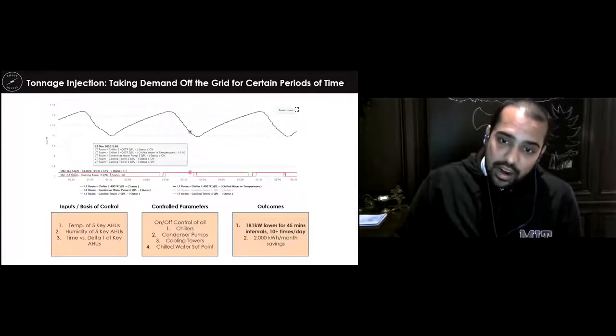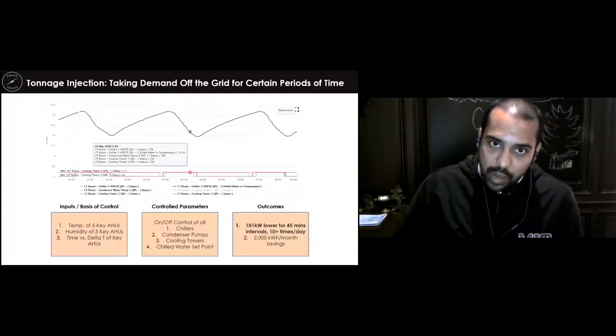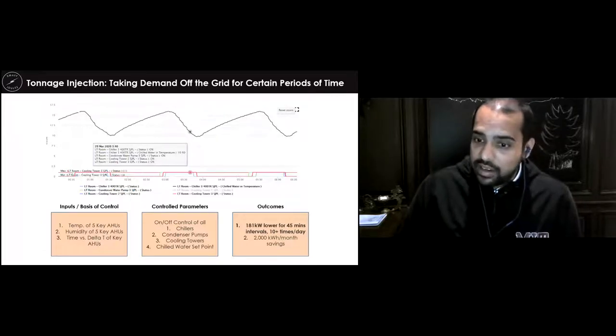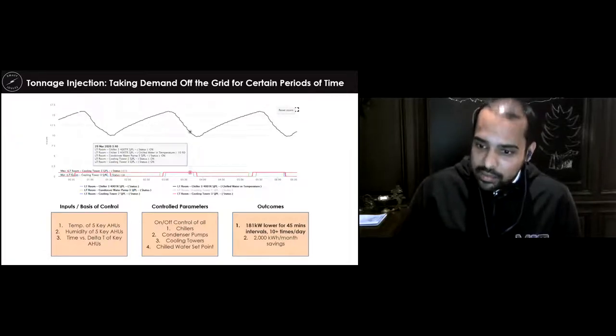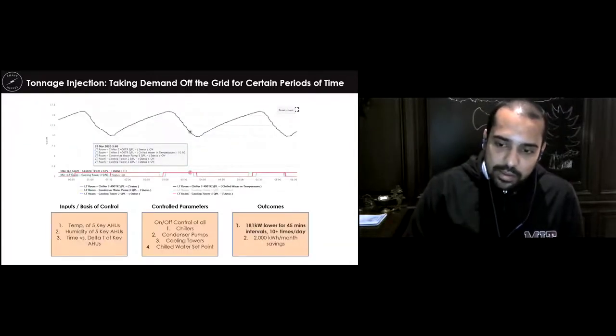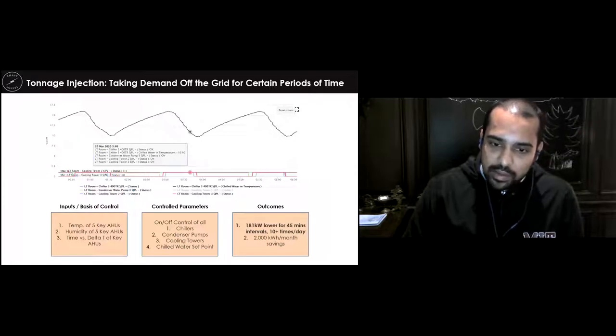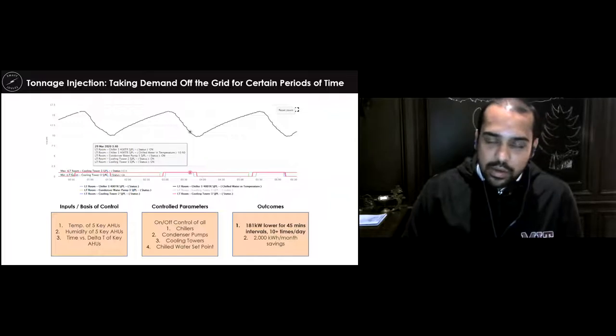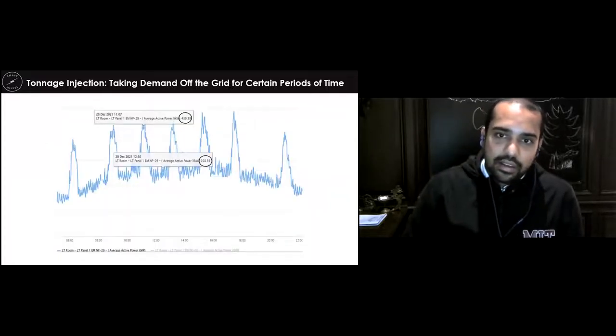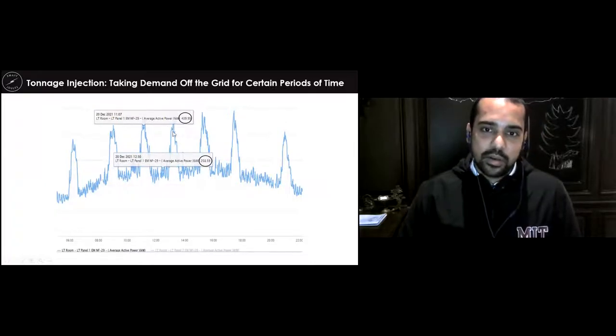In this particular example, 181 kilowatts of power were taken off the grid for 45 minute intervals each, more than 10 times a day. Typically you think it's only demand response, but because you're taking off condenser pumps and cooling towers as well, it actually results in energy savings too, not just power reduction. So here's a curve. You can see 440 kilowatt, and you do this tonnage injection, and the consumption at that moment is high because the chill water set point is low. You're overcooling the building.